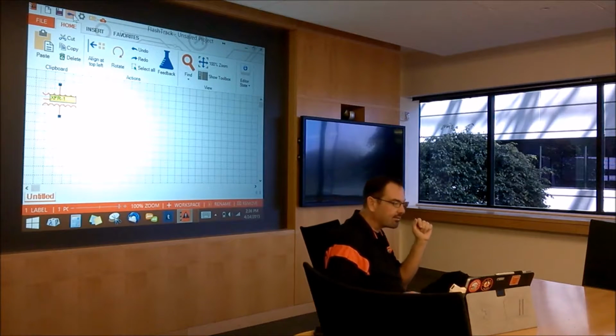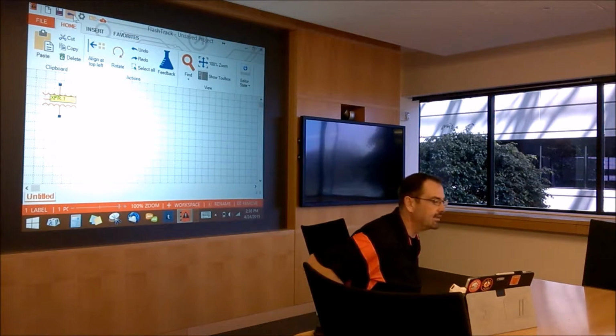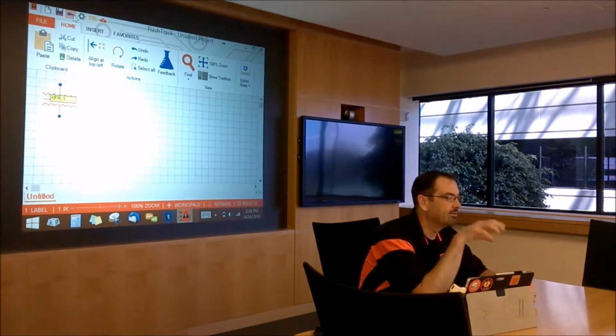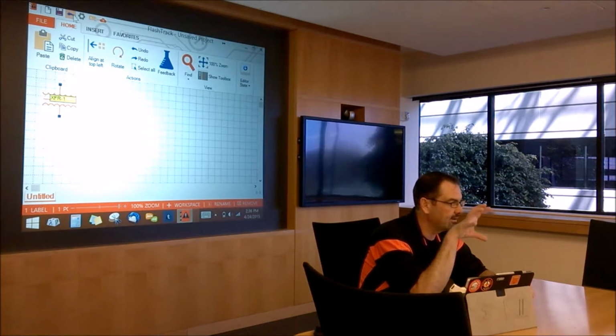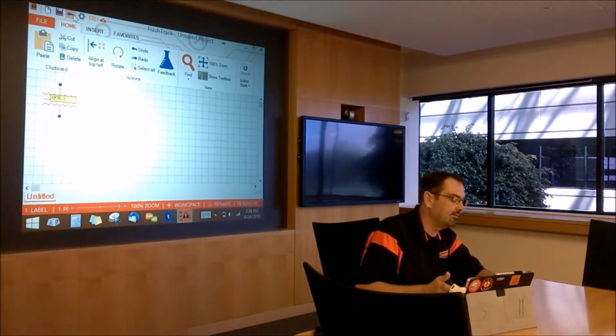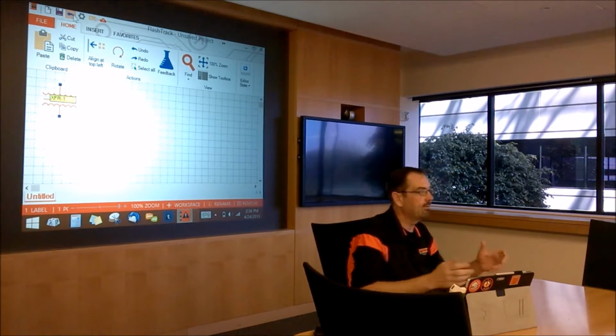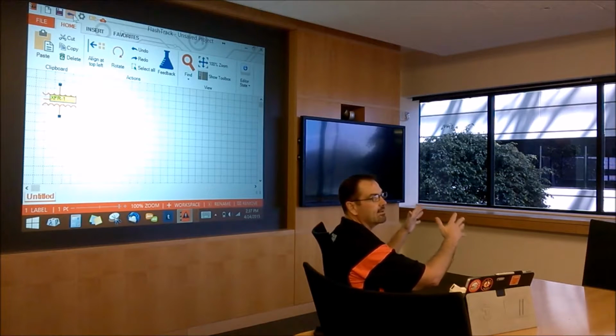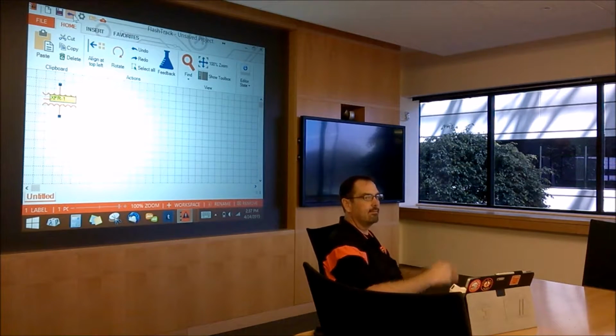When we train electricians how to do the data collection, a lot of times we're working with electricians that do electrical preventive maintenance, and they've got some software where they take pictures of stuff. But they're taking pictures up close. They want to see the burnt back wires and the discolored copper and things of that nature. I don't care so much about that. For label installation purposes, we teach them to take 12 to 15 steps backwards from the components to get a nice geographical representation of where that item is located, so when we go back and put the label on it, it makes it a lot easier.